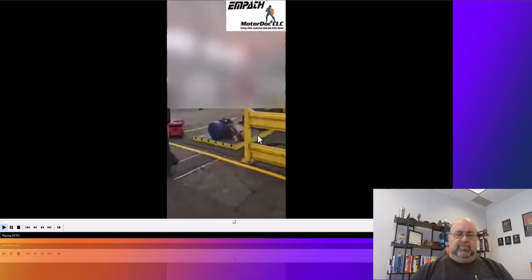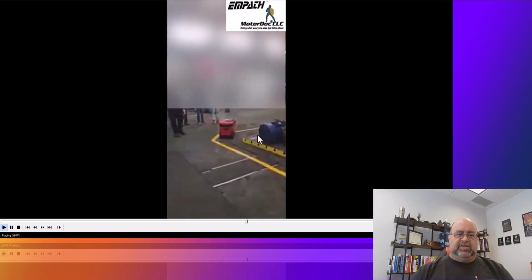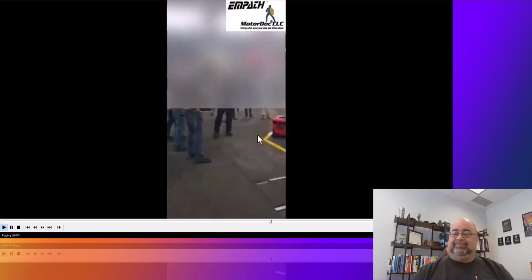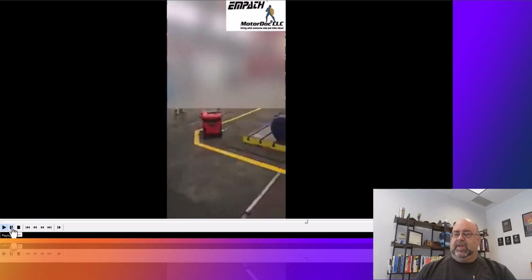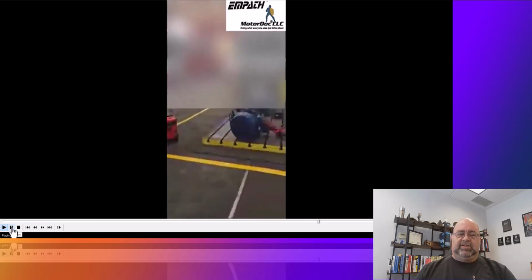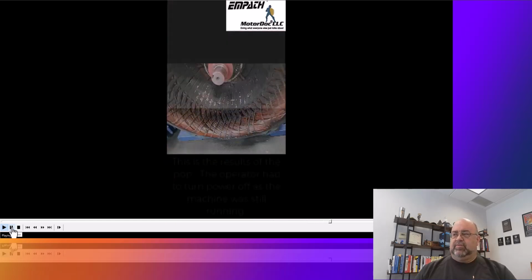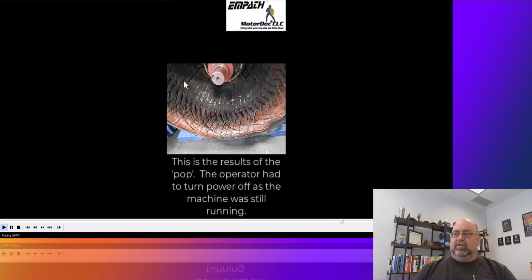What I like to do when something like this occurs is pull the motor apart and take a look and see what we see. Looks like things are lagging on me, so obviously I'm taking up way too much. The rotor scraped the stator, pulled copper out, and it blew up. Apparently it might have been doing that in place, based on what the bearings looked like.